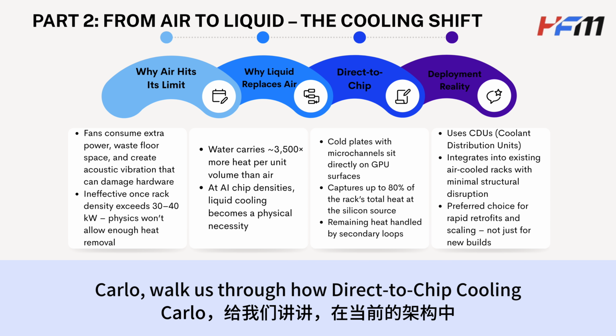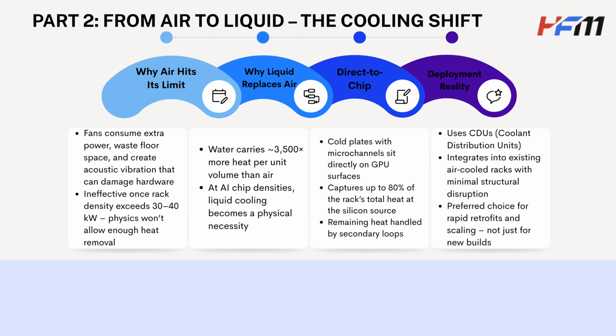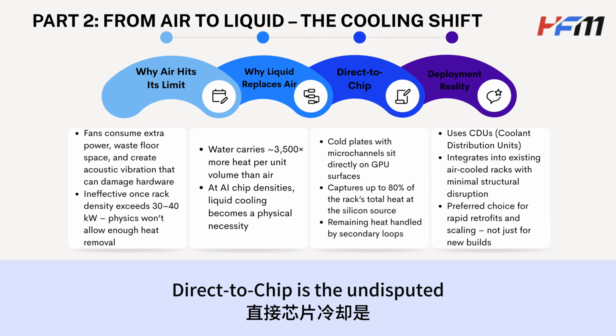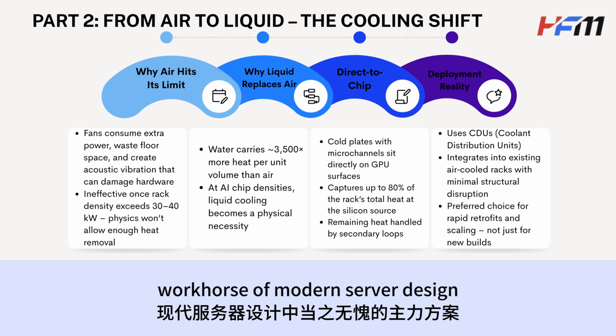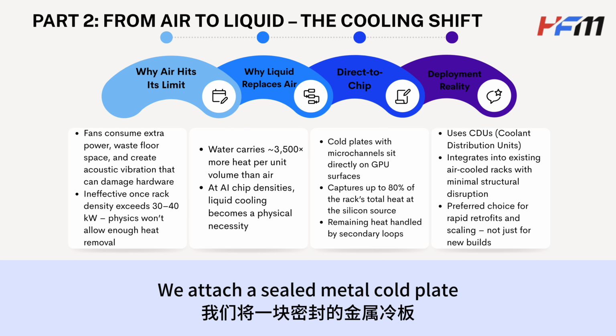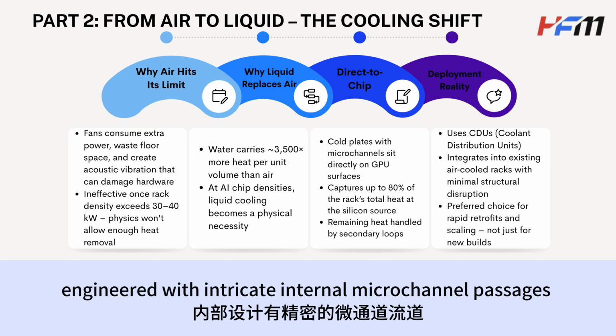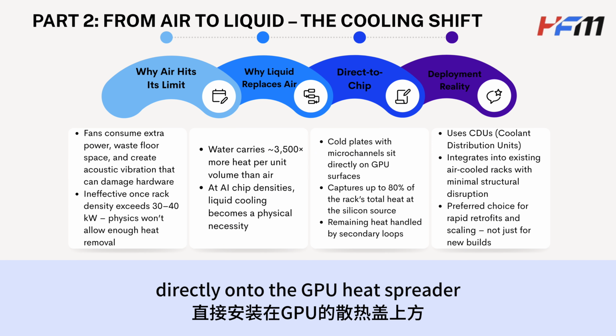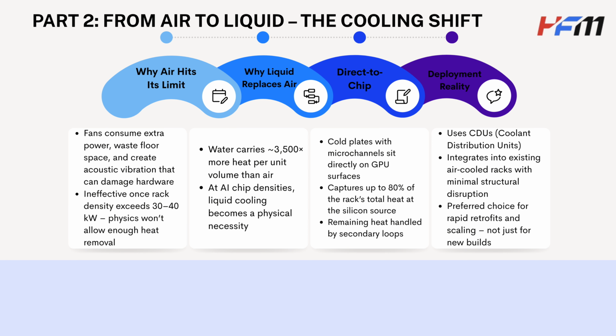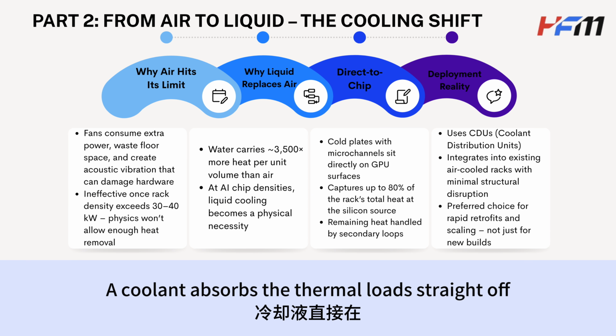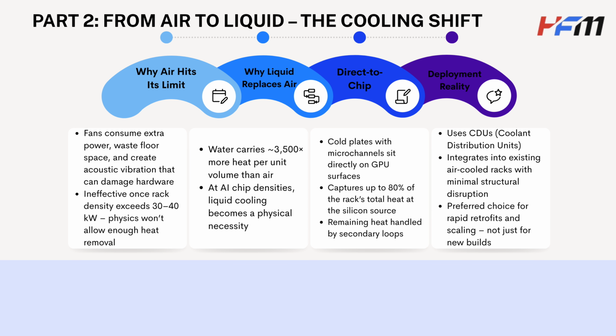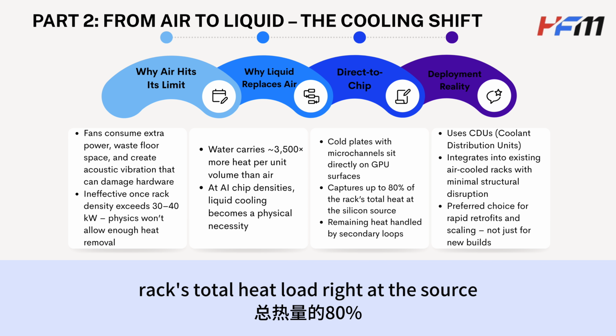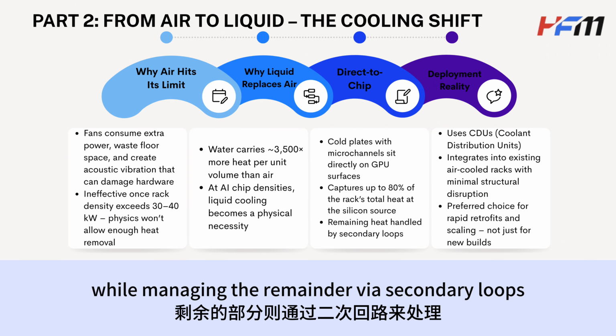Carlo, walk us through how direct-to-chip cooling is leading the architecture today. Absolutely. Direct-to-chip is the undisputed workhorse of modern server design. We attach a sealed metal cold plate engineered with intricate internal microchannel passages directly onto the GPU heat spreader. Coolant absorbs the thermal load straight off the silicon surface, capturing up to 80% of the rack's total heat load right at the source, while managing the remainder via secondary loops.